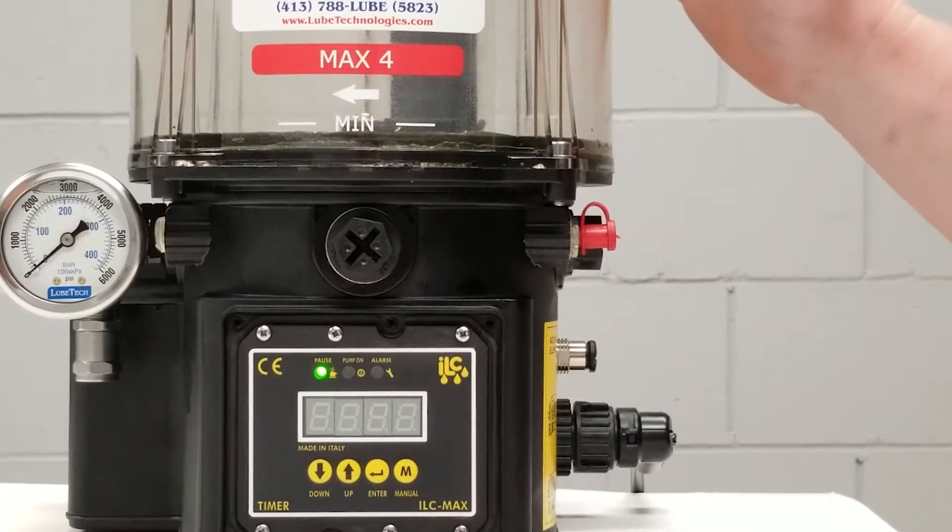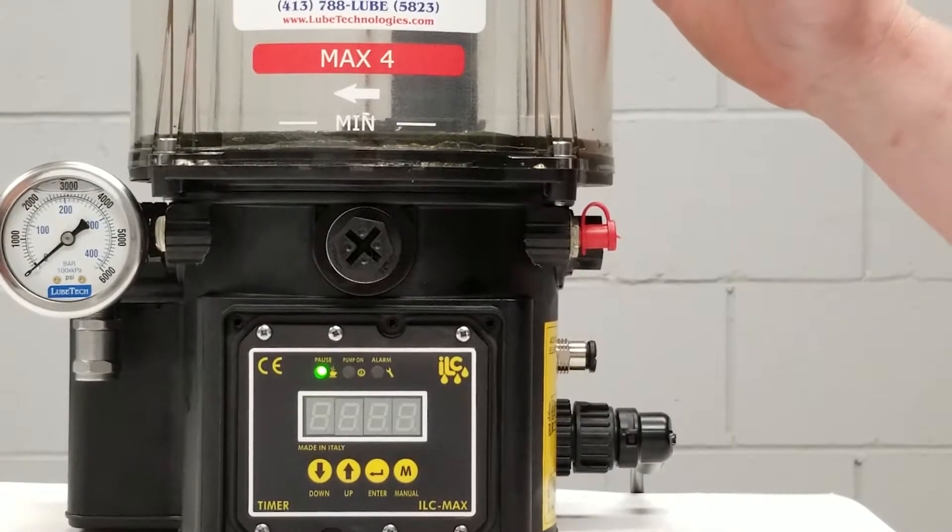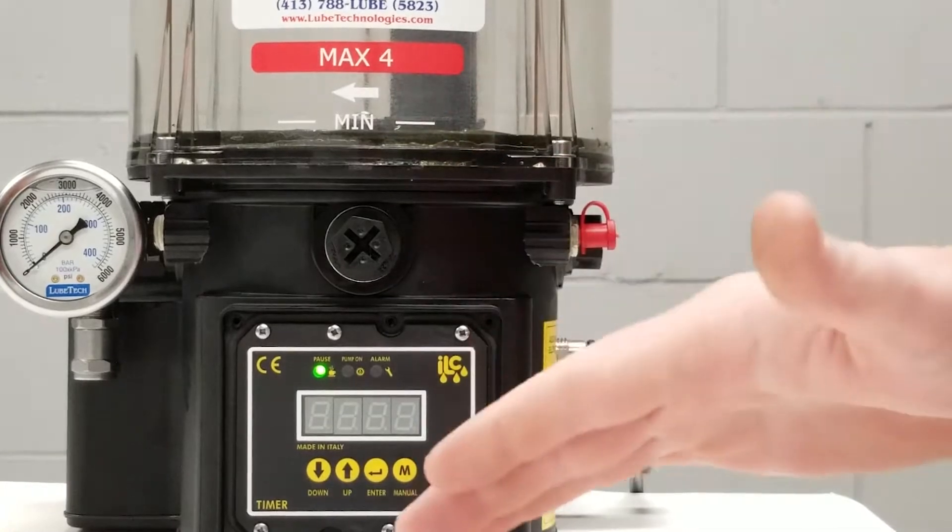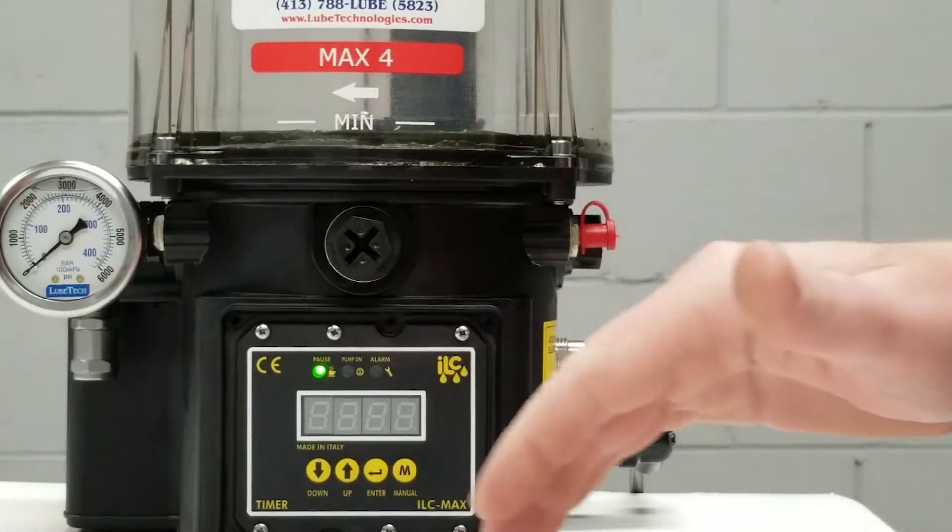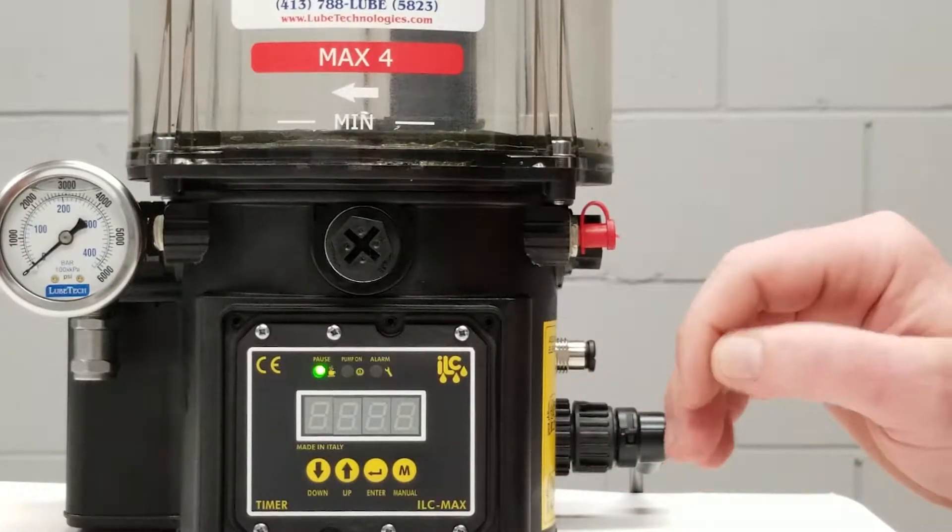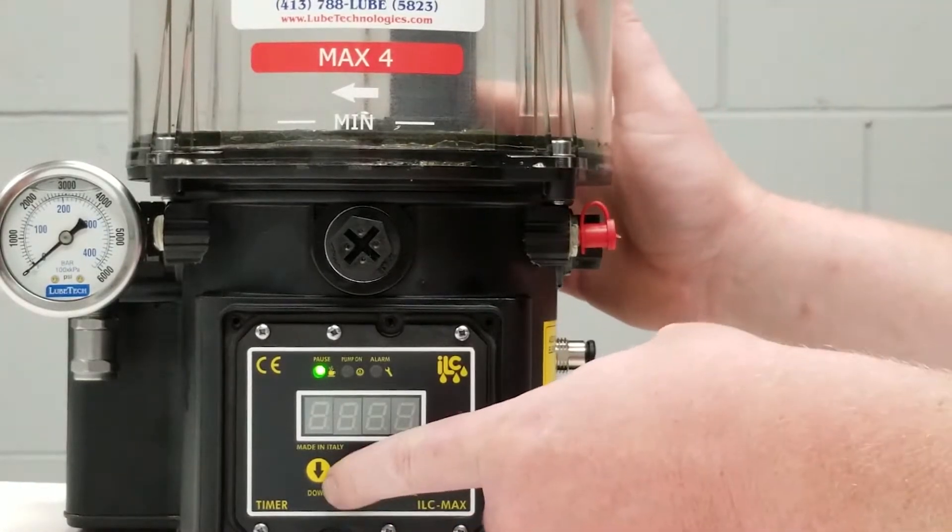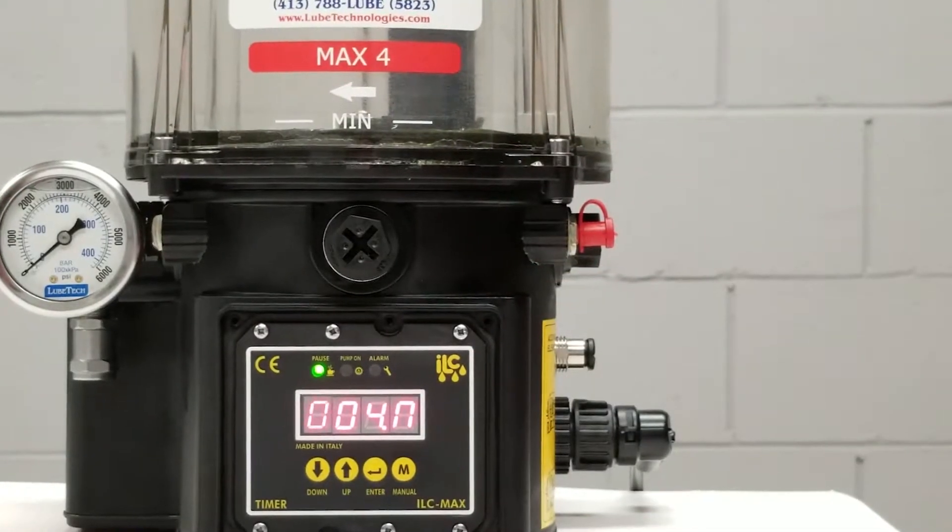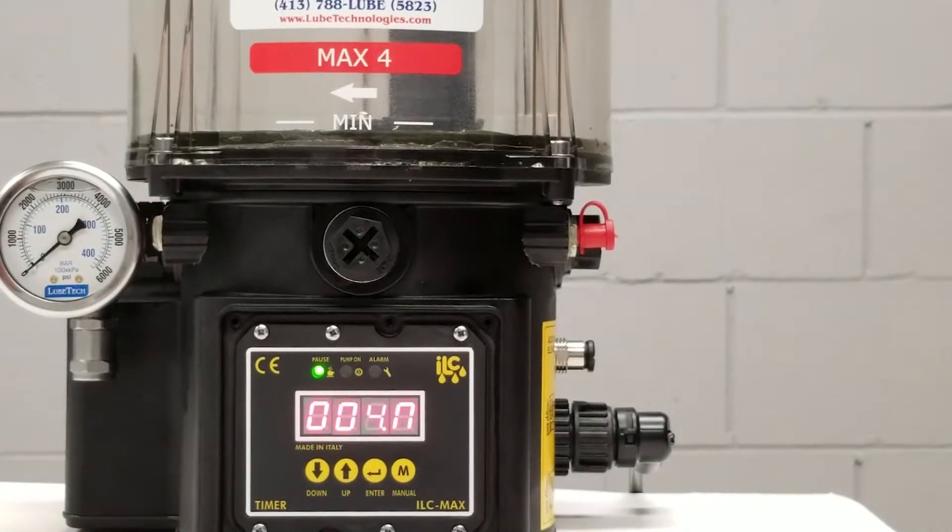To get into the programming mode we have to have the ignition on which means we need to have power to the pump and again you would know if you have power by seeing the LED status. One of them should be on. If your screen is blank and you want to know where we're at, you simply press the up arrow key and this will make our screen illuminate. This right now tells us that I have four minutes left in my delay time until this pump comes on and runs again.